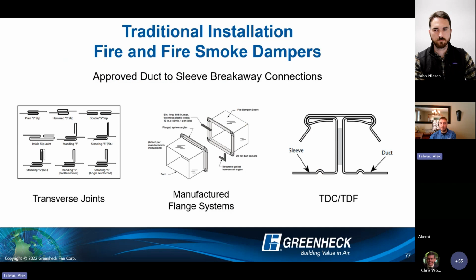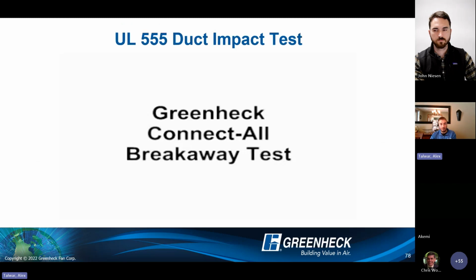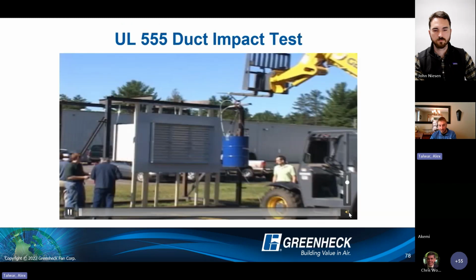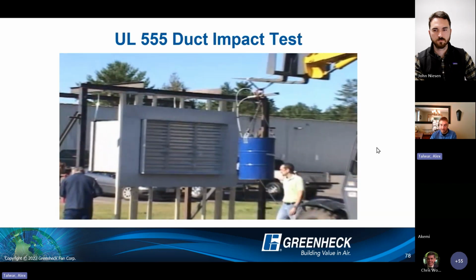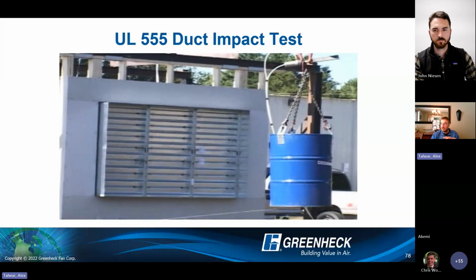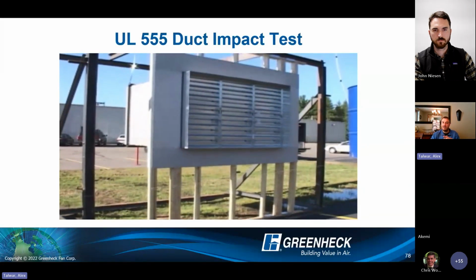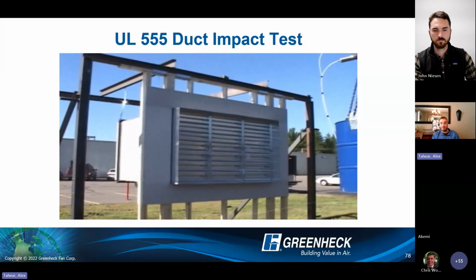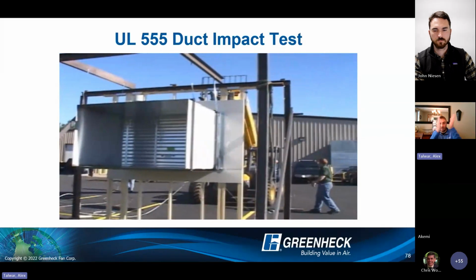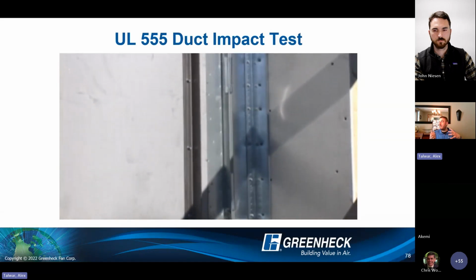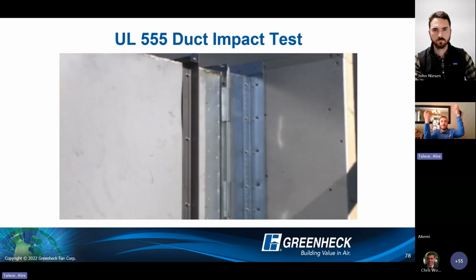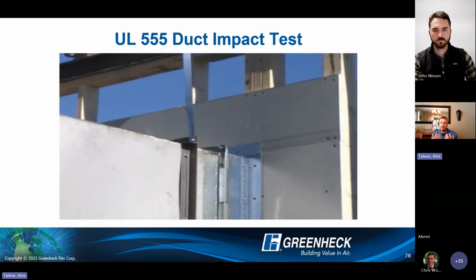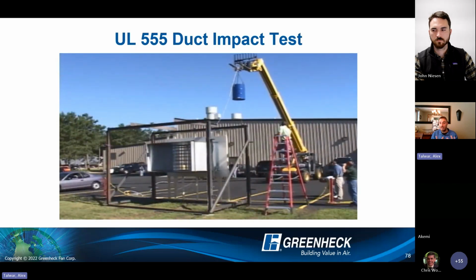And then if we are connecting ductwork to it, we need to use an approved breakaway connection. I mentioned that the damper sleeve can only come so far out of the wall before we have to make a connection. That's because we have to pass one of these tests. If I can get the video to play here. So this is a UL 555 duct impact test. Essentially, the whole reason you have to use these breakaway connections and terminate the ductwork at the damper is this: if you have a fire on a floor above you, you start having falling debris. If something falls and impacts your ductwork that's attached to your damper, you don't want that damper to be compromised. You still want that damper to remain installed in the wall and provide fire and smoke protection if necessary.